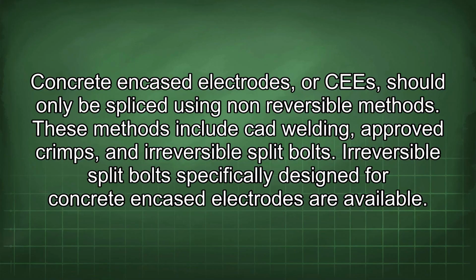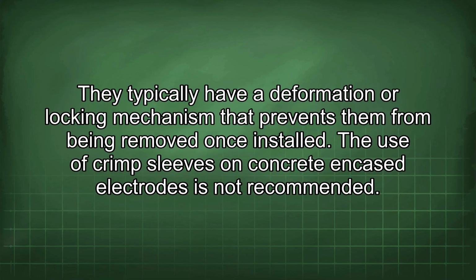Concrete encased electrodes, or CEEs, should only be spliced using non-reversible methods. These methods include CAD welding, approved crimps, and irreversible split bolts. Irreversible split bolts specifically designed for concrete encased electrodes are available. They typically have a deformation or locking mechanism that prevents them from being removed once installed.